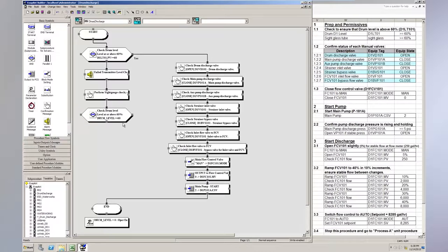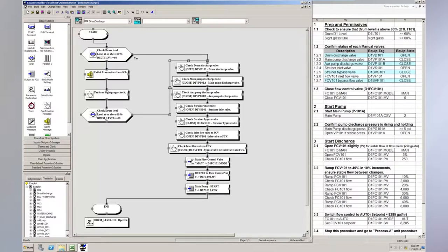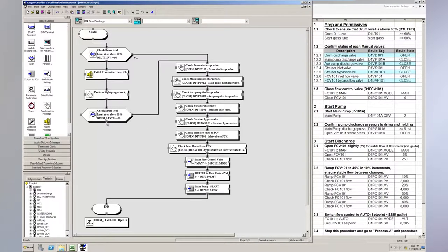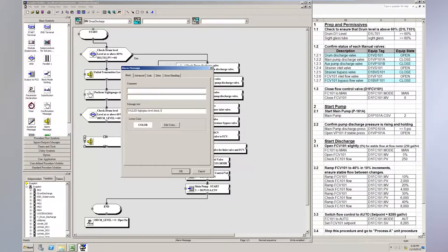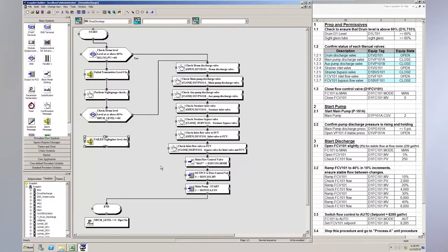It's got to pass this criteria here. And instead of looking at the DCS tag.parameter, it's coming from the OPC server. I'm now going to use the variable that the operator entered to do that check. And then if it passes this, then I want to then go back into the valve lineup. So I can wire this to the same node that the transmitter drum level check is going to. You can have multiple lines wired to the same node. If it fails, let's go ahead and do an alarm on that. Then we're going to say failed sight glass check. Fill drum and restart. We'll make this red. Now I'm going to wire the no decision here. So I need to characterize this flow as no. And I need to characterize this line that I put into the valve lineup as yes.